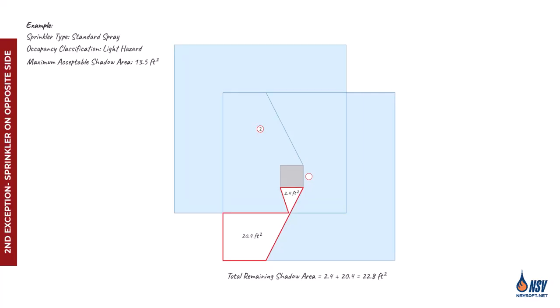Next, we apply the same procedure to sprinkler 2. This sprinkler covers a larger portion of the shadow area compared to sprinkler 1. However, the remaining shadow still exceeds the acceptable limit, so sprinkler 2 also cannot be considered the opposite side sprinkler.